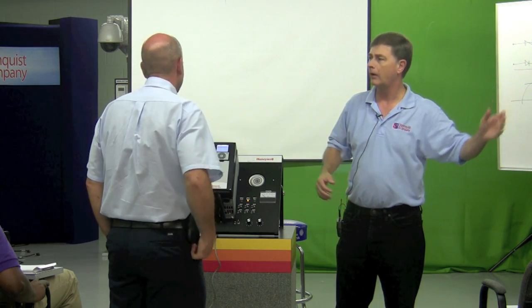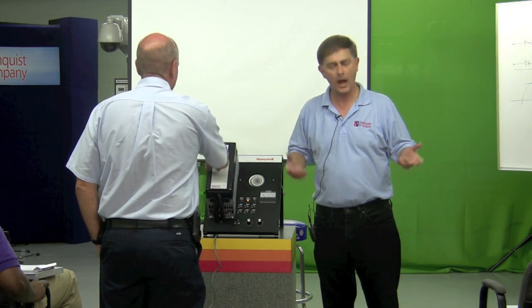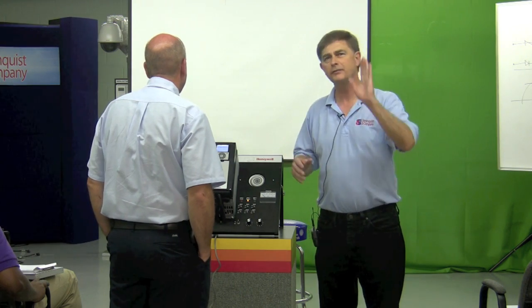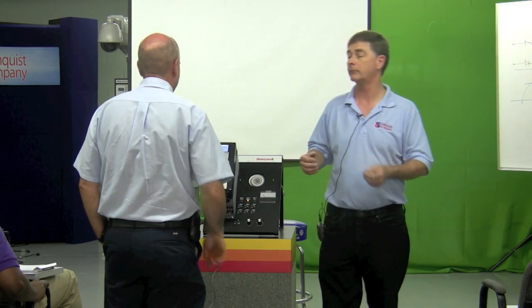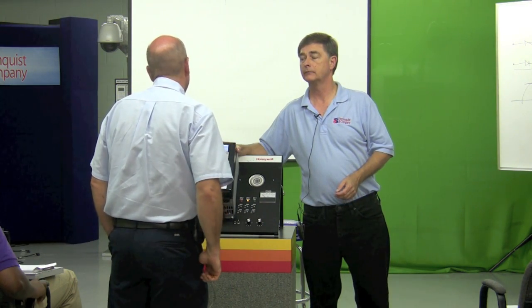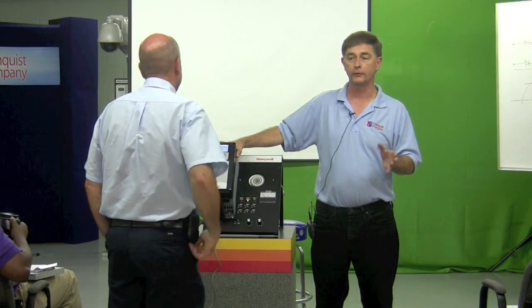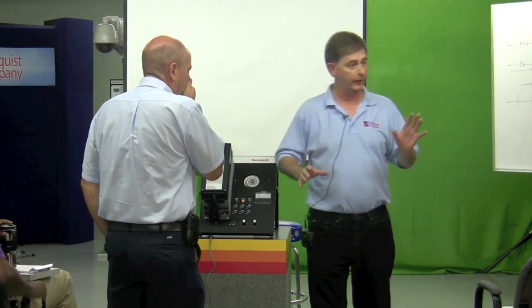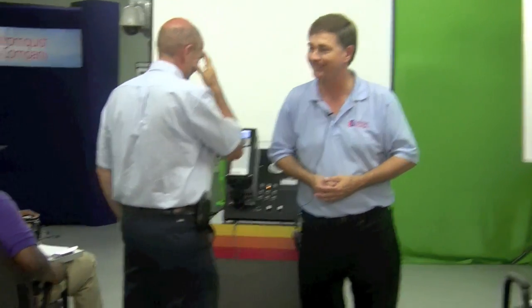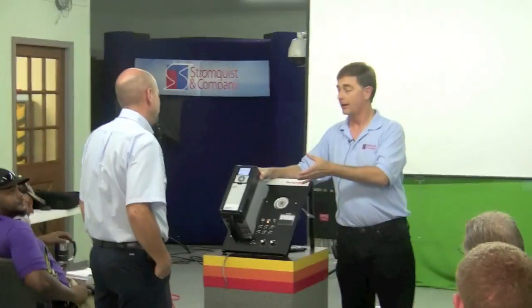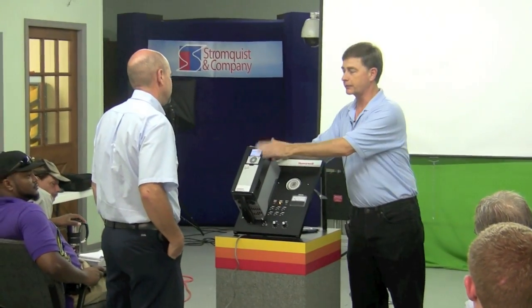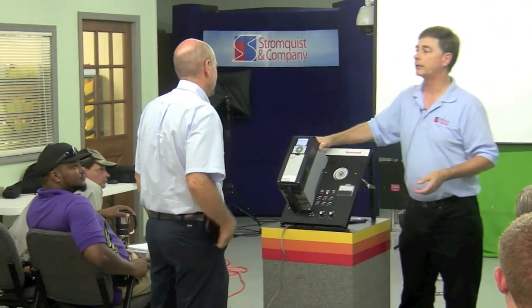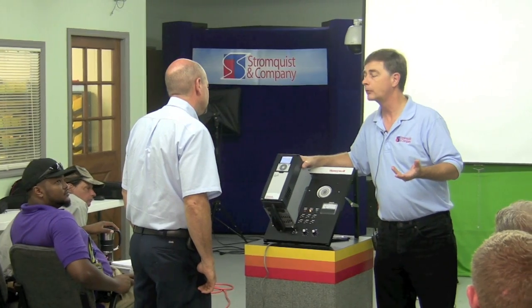It's asking for preferred language — go ahead and hit OK for English. Now it's asking for region — go with US. We'll skip the time and date, it doesn't need that to run. There's a startup wizard and it's going to ask some very straightforward questions. It asks what type of load — let's call this a fan, hit OK. Now it asks for RPM — look at the motor nameplate and hit OK. Enter the nameplate amps and hit OK. Ready to start — hit OK.